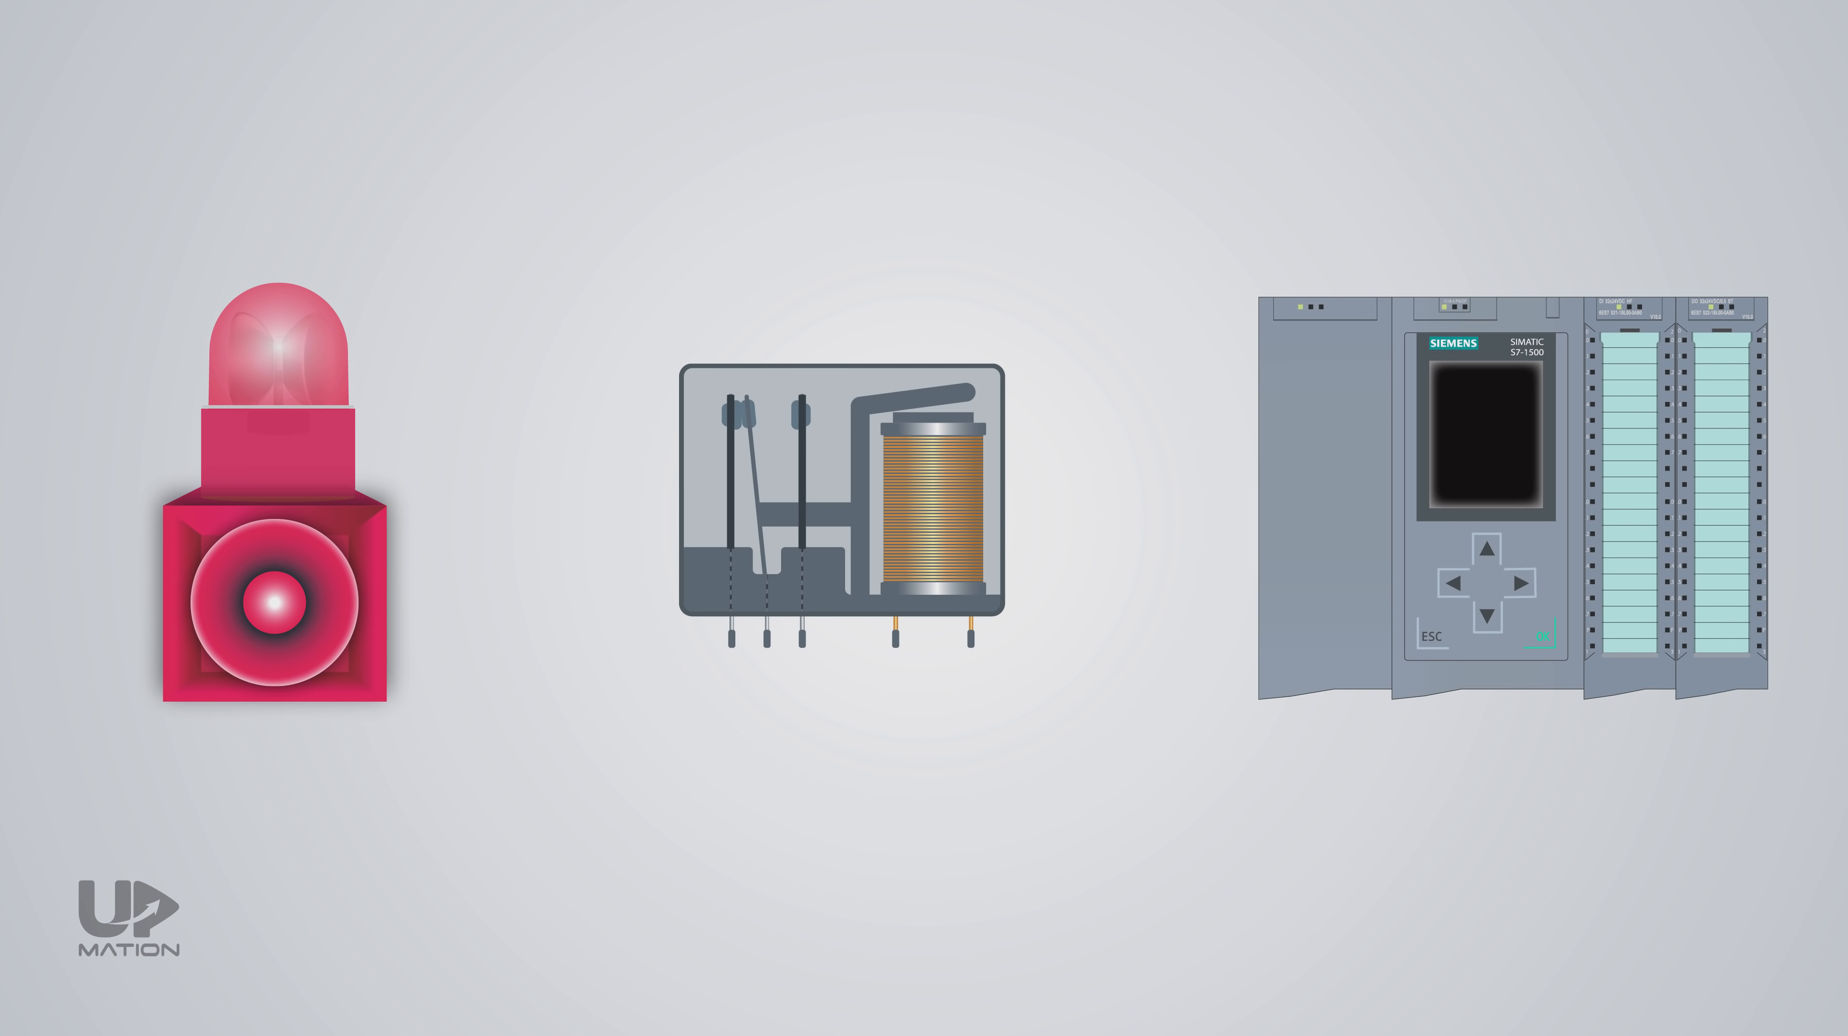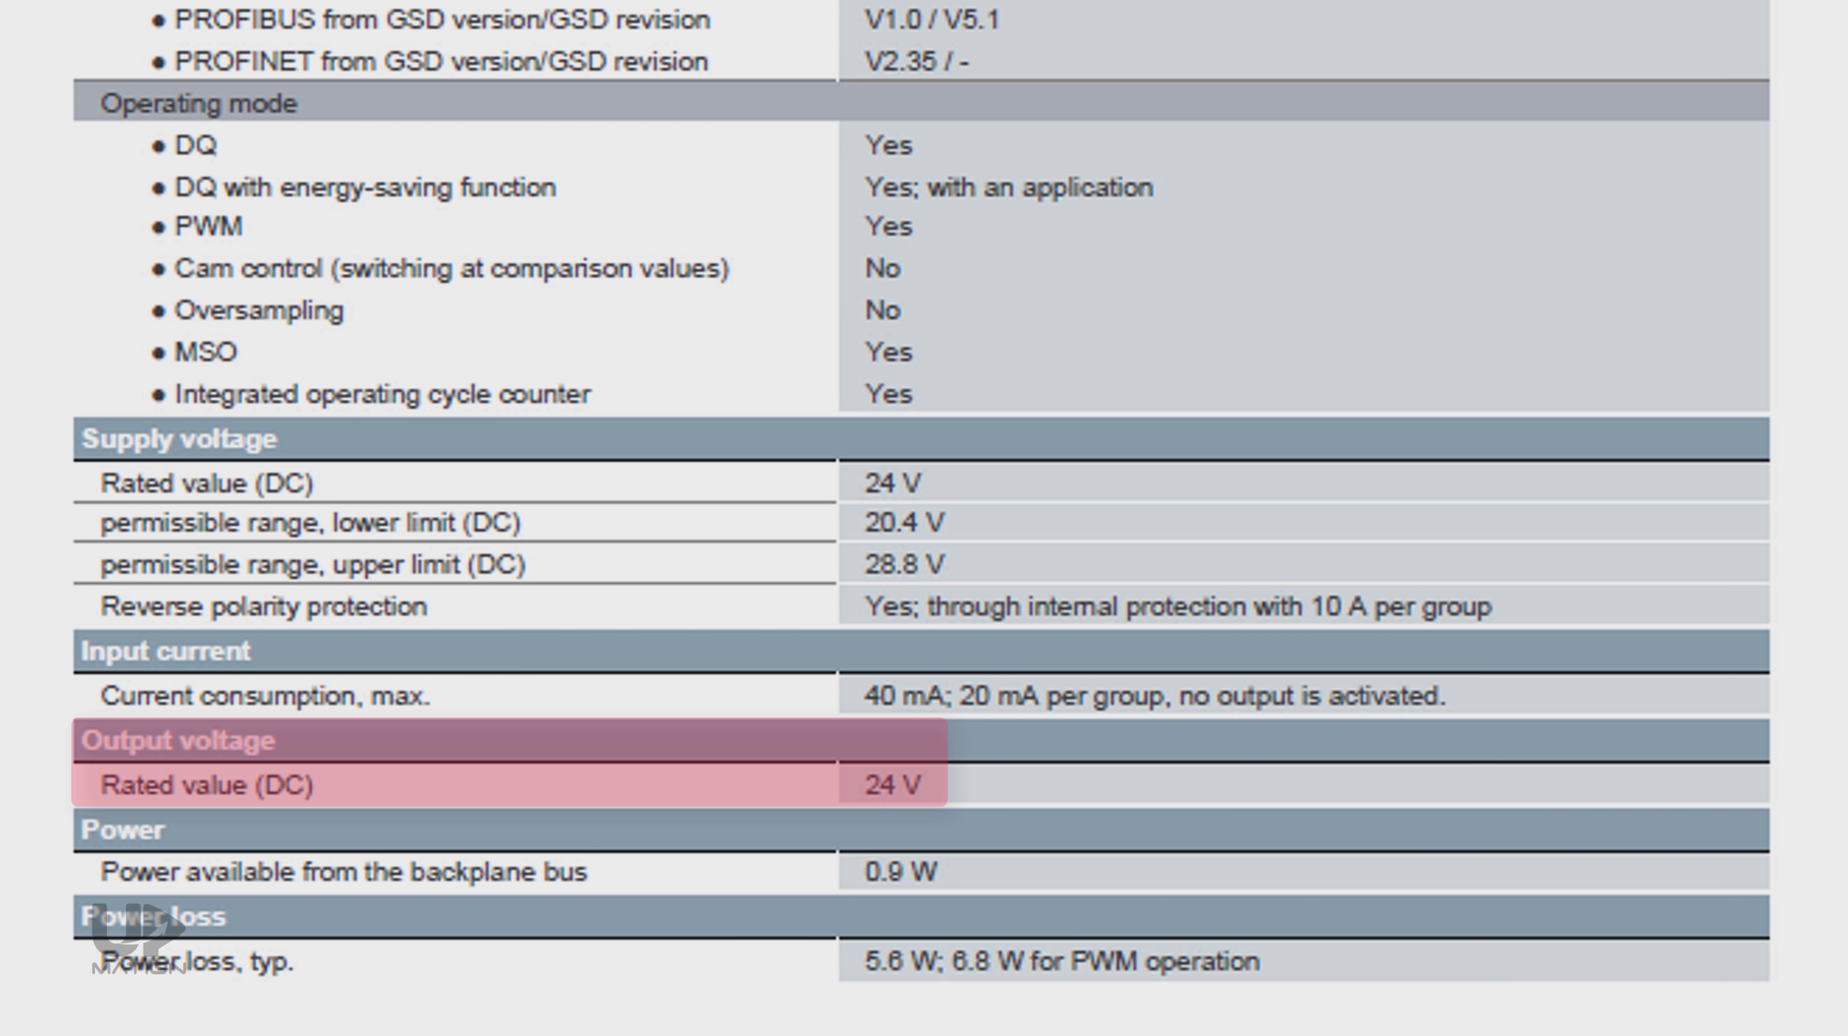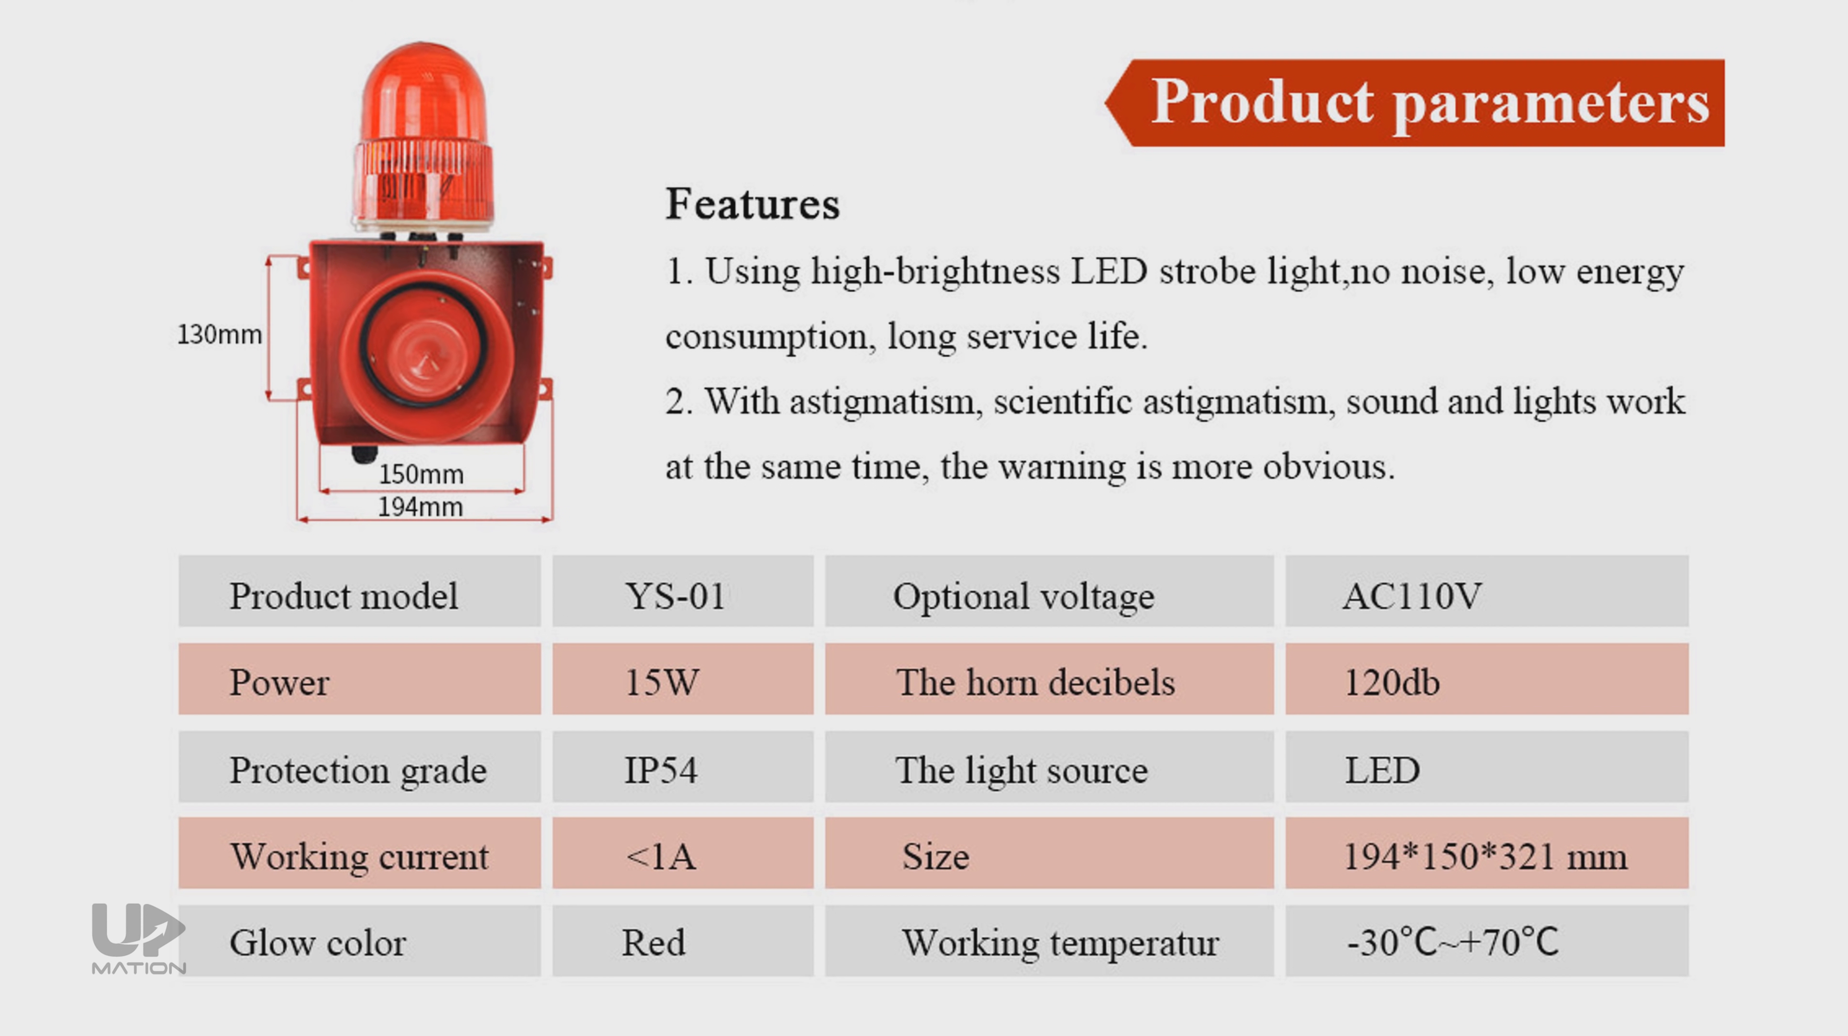For instance, if we want the PLC to turn on this siren alarm according to its logic, we should first check which control voltage signal the PLC card sends out. Let's assume it's a 24 volt DC signal. Then, we'll check the siren's power rating. For example, it is 110 volts AC with about 1 amp of rated carry current.